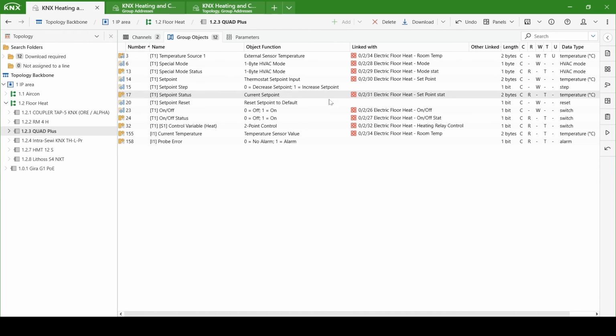We also have the output that's going to drive, in this case, our RM4 relay, and that relay is going to be joined so that when the set point's below the target, it's going to turn on, and when it gets above, it's going to turn off. You can watch that happen.